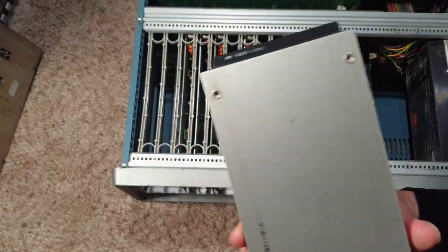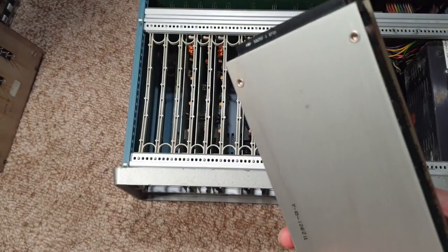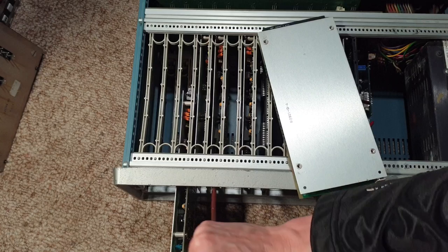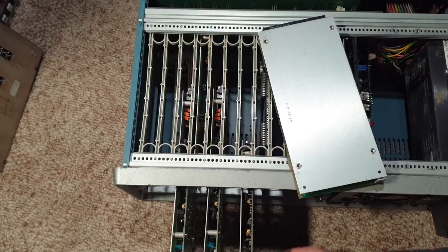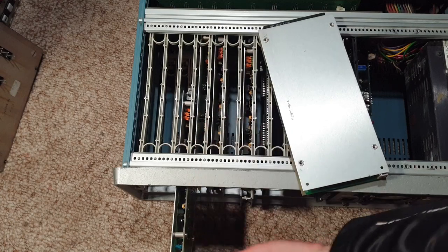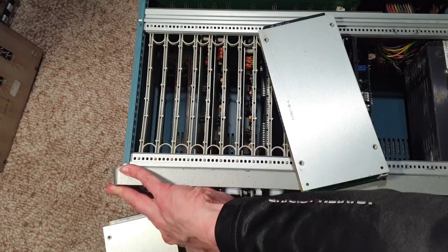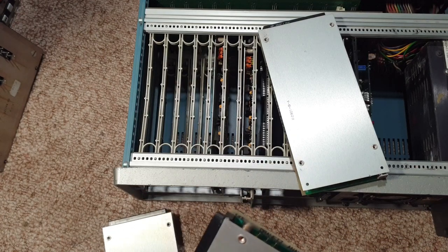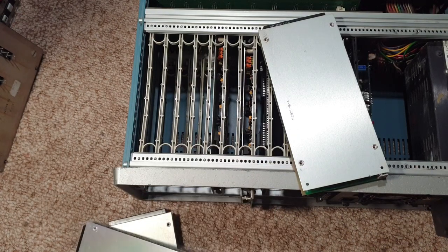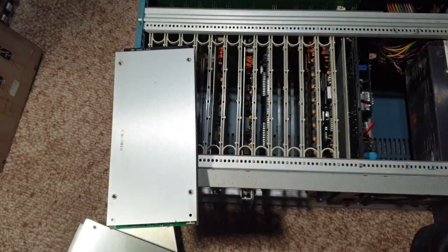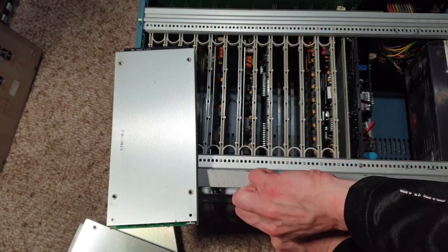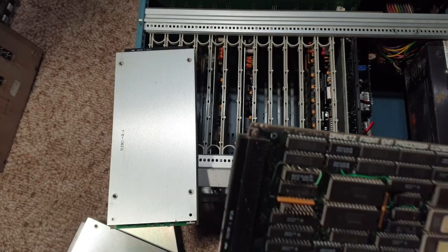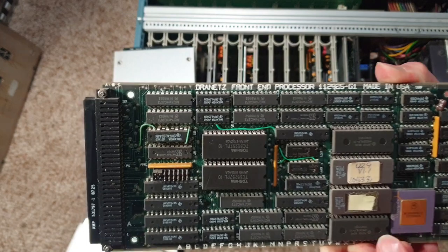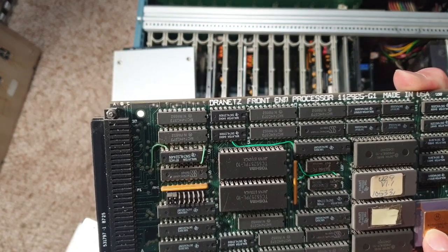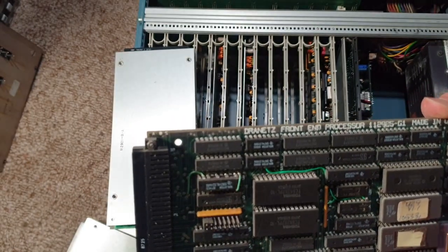So each input has got one of these, which is called a channel input. There's four of those, three phases and then an auxiliary channel. Then there's this other one that they call analog to digital converter. So these also have covers on them, we'll just get that off. And I think there's only one of those. Then we've got this, it's called a front end processor. It's got a Motorola 68000 CPU on there, some ROMs and some RAM, and then a whole bunch of logic chips.